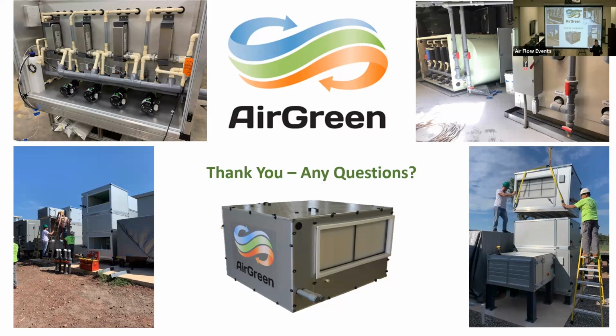ASHRAE and the school districts have all said, we need more fresh air. More fresh air means better learning environments, means all these great attributes, right? And so they want to pump more fresh air into traditional mechanical systems that can't handle it. So I want to have a project where I demonstrate that you can pull more fresh air into your school because I am treating it before it goes in. So all the consequences of moving that air through a system that's not capable of handling that increased load and moisture, I can demonstrate, you're only adding a little bit of equipment, and we can help.